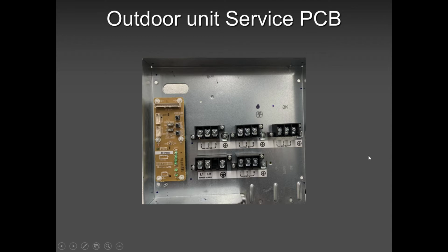That picture is what you will see when you open up a multi-zone unit, whether it's a 2-zone, a 3-zone, a 4-zone, or a 5-zone. You will see that service PCB over there. In this case, this picture is for a 4 zone. I took a picture of a 4 zone, even though the slides are of a 5 zone. This is your incoming power, okay? A, B, C, D. A zone, B zone, C zone, D zone, and if it was a 5 zone, there would be an E zone here, or somewhere on top. Okay, guys, it doesn't matter. So now our next few slides will focus on this board. I will explain to you one by one what it does.